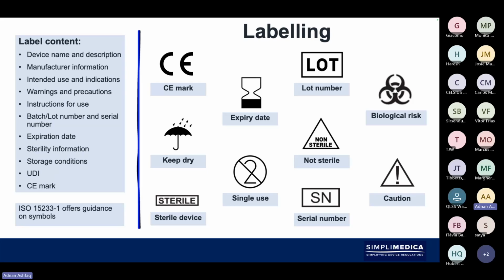That's 223 or 233? Yeah, it should be, that's the typo. ISO 15223-1, not 15233. That should be 223. And also the medical device symbol, the MD symbol.